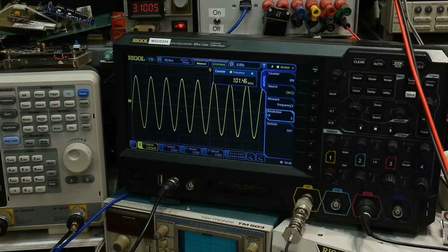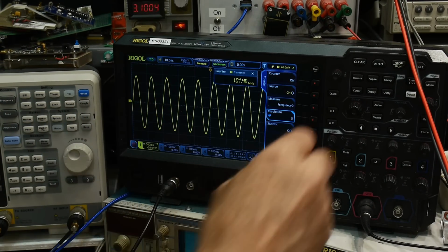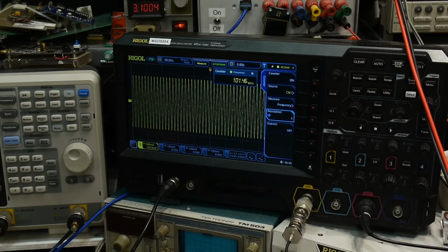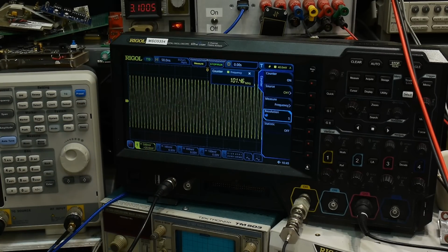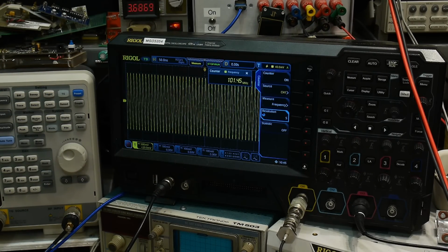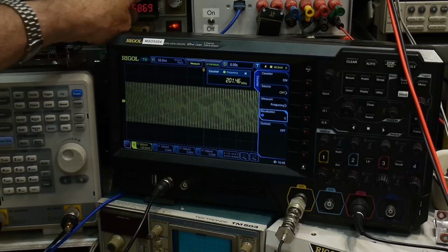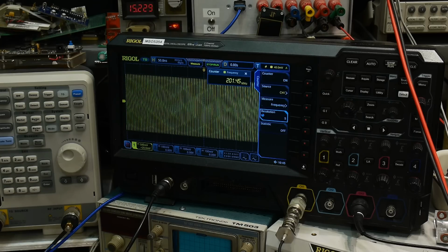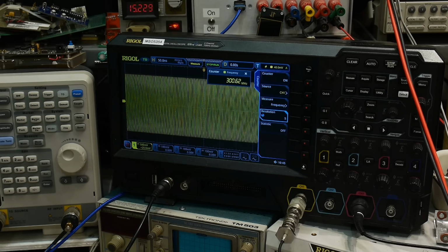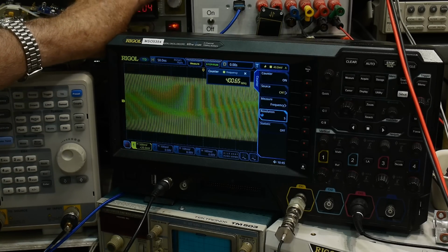What I can see is at 100 megahertz, there's some amplitude level, I'm just going to call it from that tick to that graticule. If I adjust the input attenuator, let's say that's where the level is, and that's where the leveling circuit should do it. If I go to 200 megahertz, you see it's down, so we can use the attenuator and bump that up again. We're up around 15 volts now on the attenuator. Then if I go to 300, it's about the same. Oop, 400 is too high, so we need to add some attenuation to bring it back down. We're at 3.7 volts. You can see this is all working great.